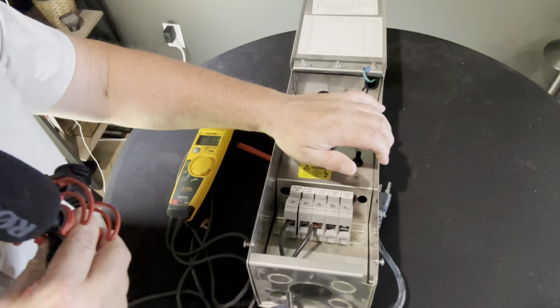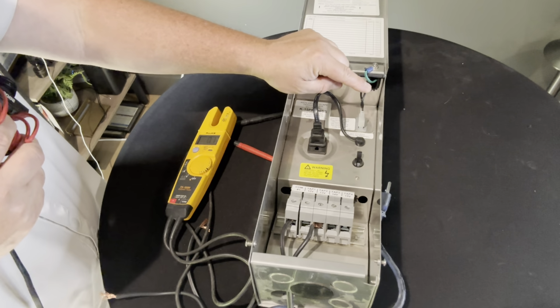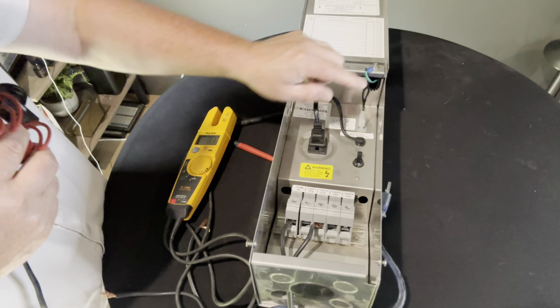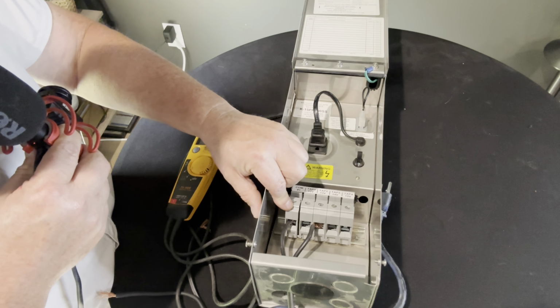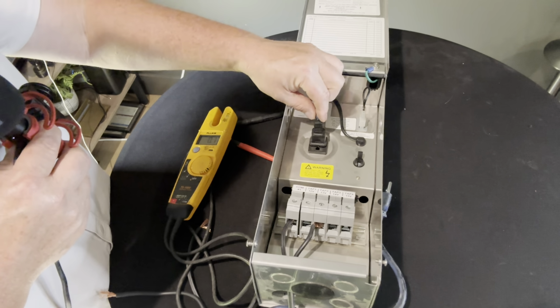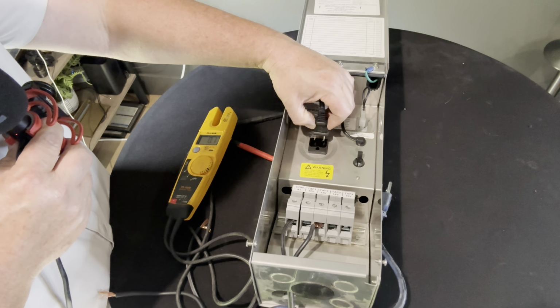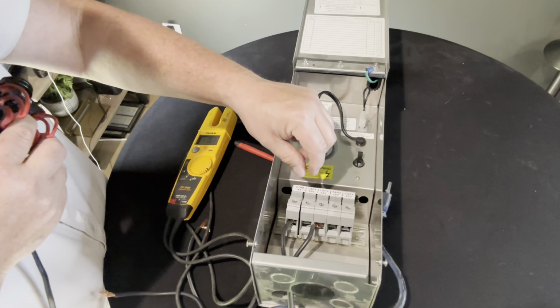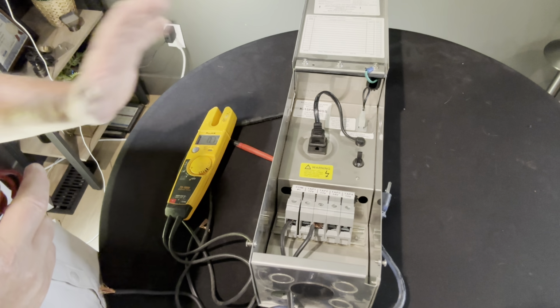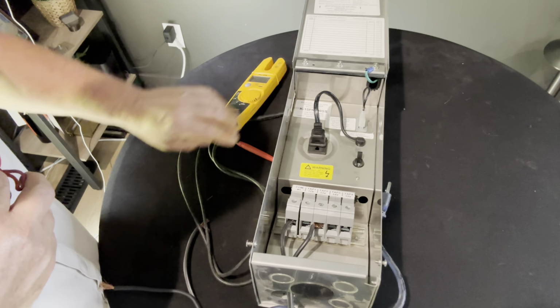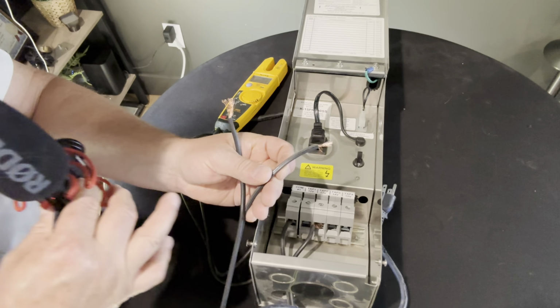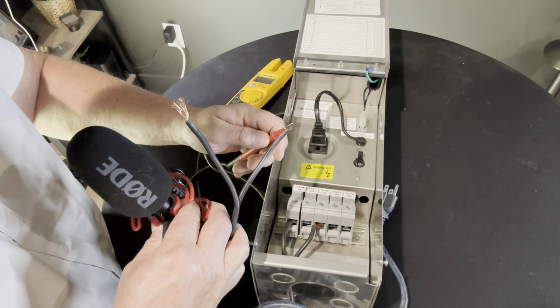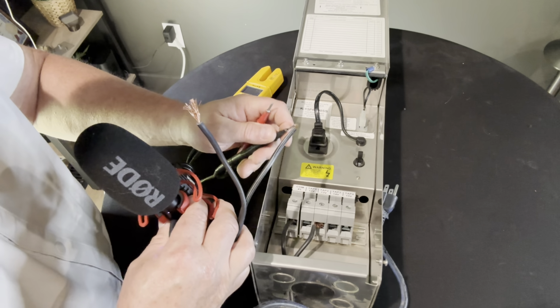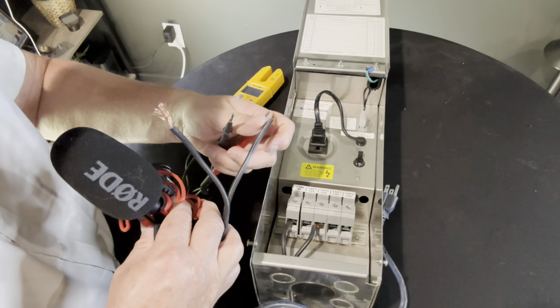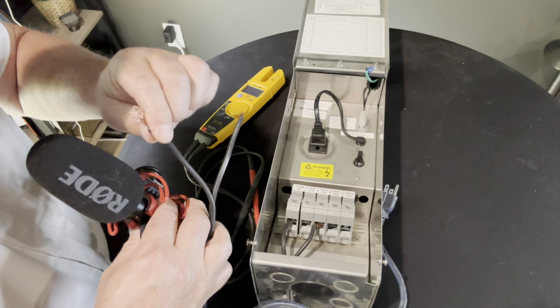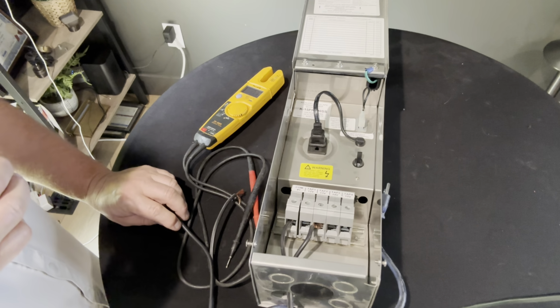So the final thing that you're going to test for, because now we've tested our amperage on the primary side, we've tested our amperage on the low voltage side or the secondary side, we tested our voltage at the outlet here, and we tested our voltage on the secondary side. So now the fifth thing that we're going to test is the wire that comes out of it. So if I were in the field, I would take my meter and I would come over here and take both of my probes and test this wire, and I can't do it because I'm holding my mic, but I would test this wire to see what my voltage is. Now that's what you're going to do when you're out in the field.